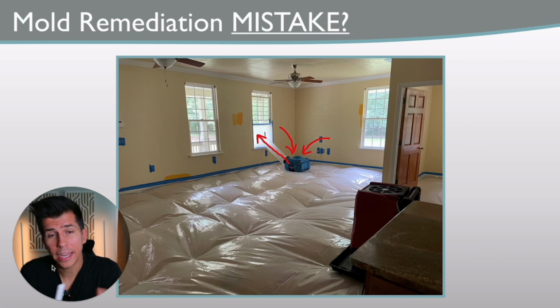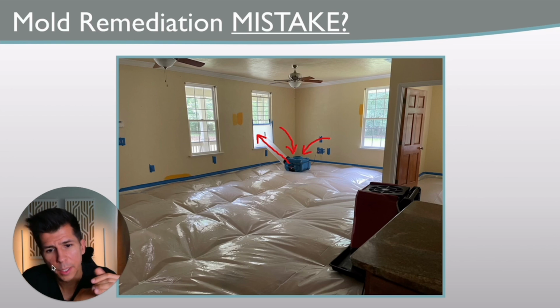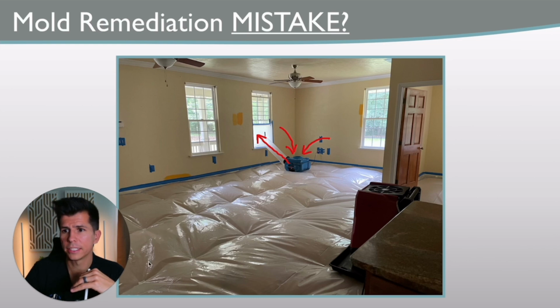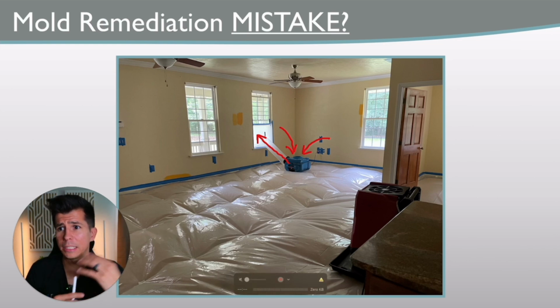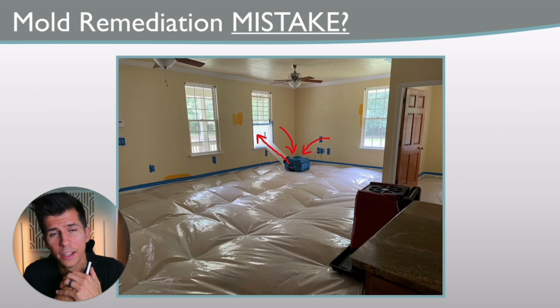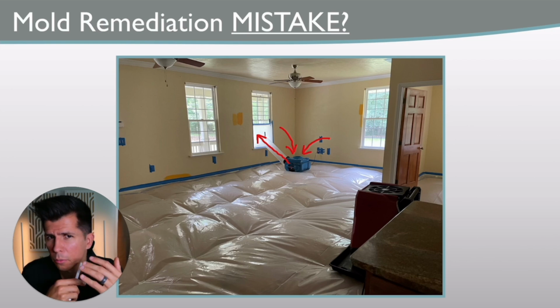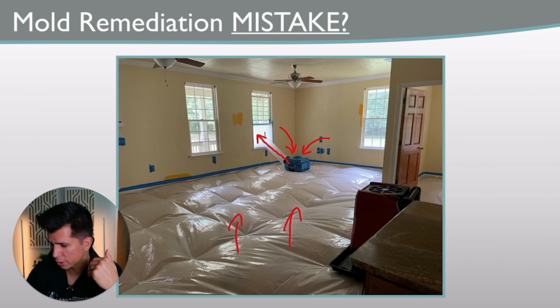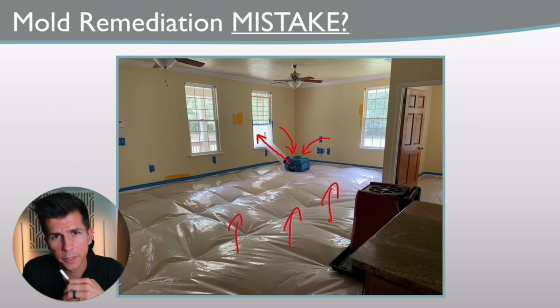Well, this is a very air leaky house. And so as they're running negative air pressure, they're pulling crawl space air in. And this is what happened. They were pulling all this crawl space air in, and this is what the technician's supervisor told me. The technicians would call them up. Hey boss, we're dealing with this house and it's getting really musty smell. It smells like a crawl space in here. We don't know how to stop it. Why do you think it smelled like a crawl space? Because you're running negative air and you're pulling all this crawl space air through this leaky subfloor.